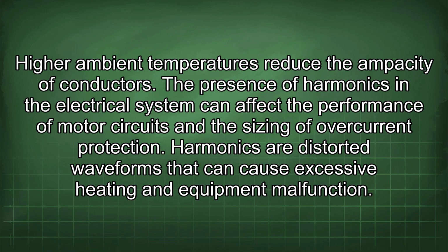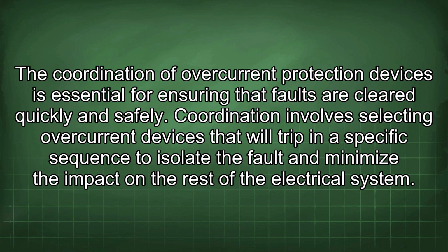The presence of harmonics in the electrical system can affect the performance of motor circuits and the sizing of overcurrent protection. Harmonics are distorted waveforms that can cause excessive heating and equipment malfunction. The coordination of overcurrent protection devices is essential for ensuring that faults are cleared quickly and safely. Coordination involves selecting overcurrent devices that will trip in a specific sequence to isolate the fault and minimize the impact on the rest of the electrical system.